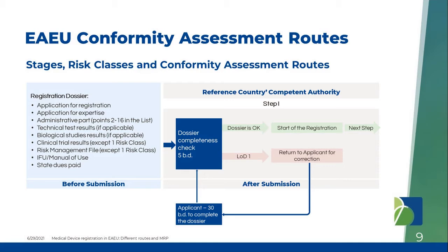Risk management file, as I said before, is a very important document. It was repeatedly noted by our authorities that risk management is a cornerstone of the Eurasian Union registration system. That's true enough for any medical devices registration system. Of course, now we are providing the risk management file and process failure modes and design failure modes and effects analysis during the national registration. But in Eurasian Union registration, it's an obligatory requirement. So it's the cornerstone of the registration to provide the full risk management file.